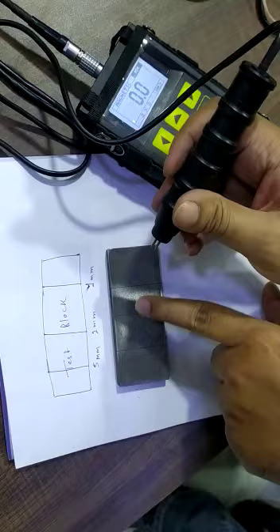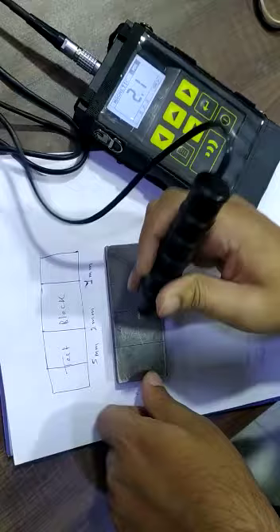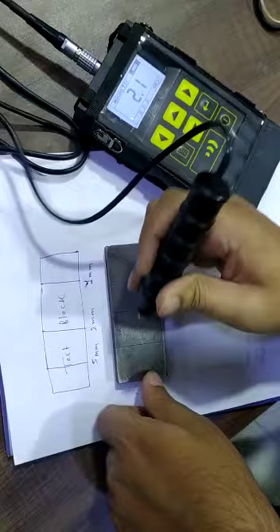Now we will test 1 mm, 2 mm, and 5 mm depth. The 1 mm depth is measuring 1.2. The 2 mm depth is measuring 2.1, and the 5 mm depth is measuring 4.9. The machine accuracy is 10% plus minus 0.2, but the results are very good.